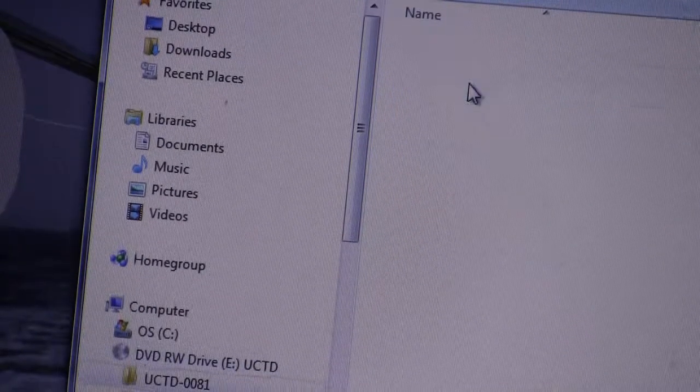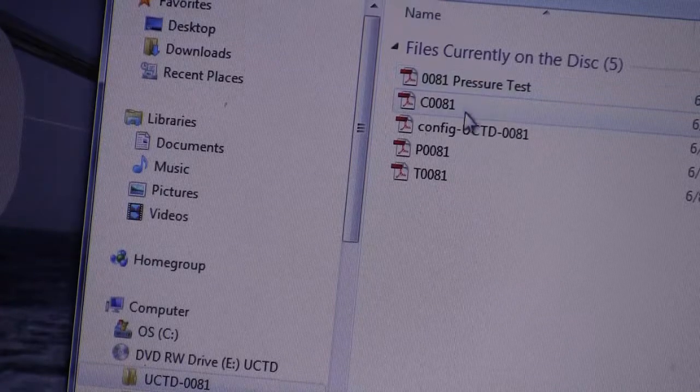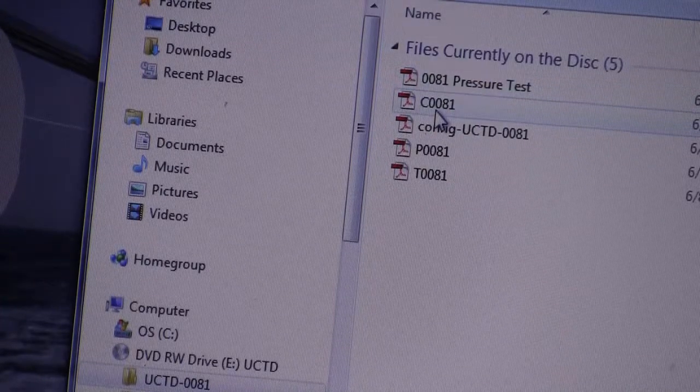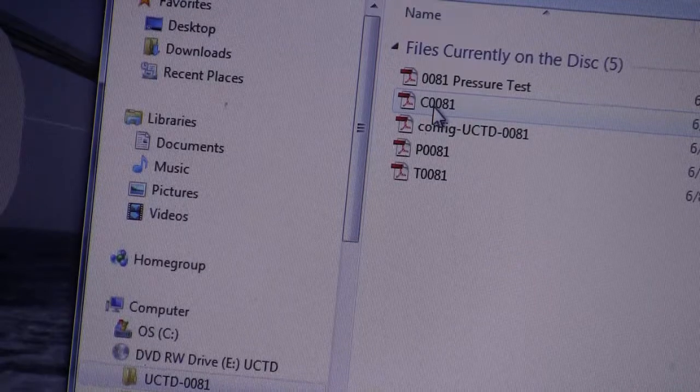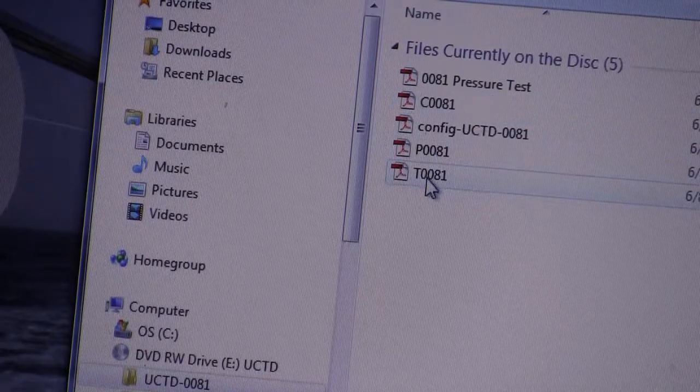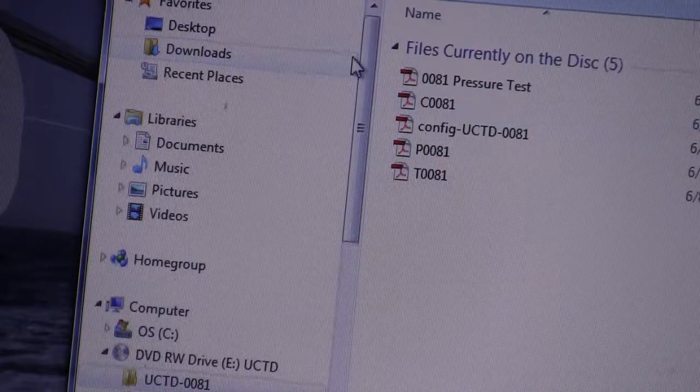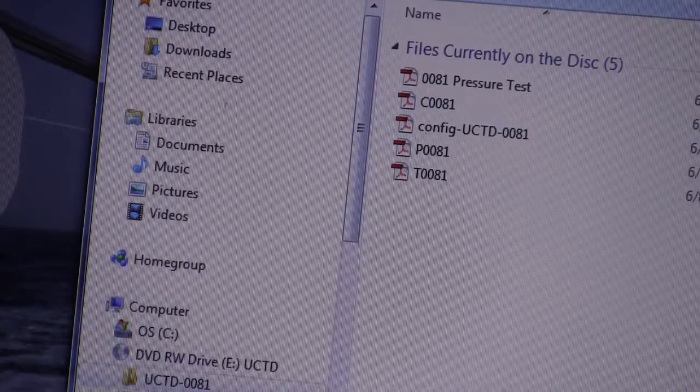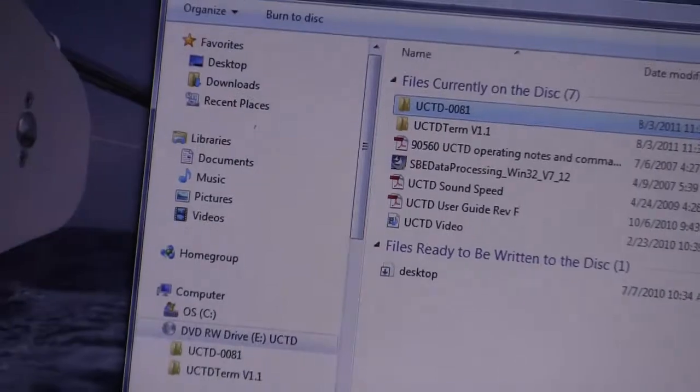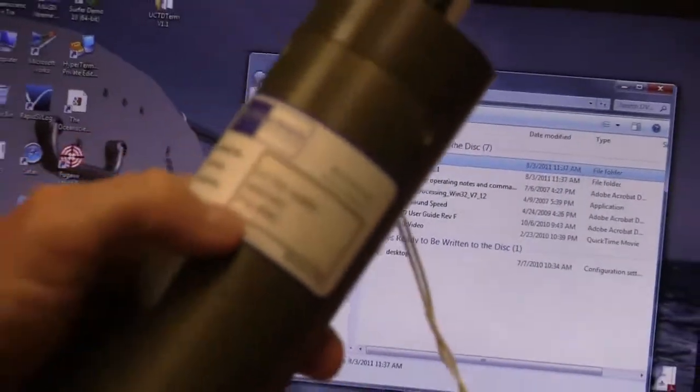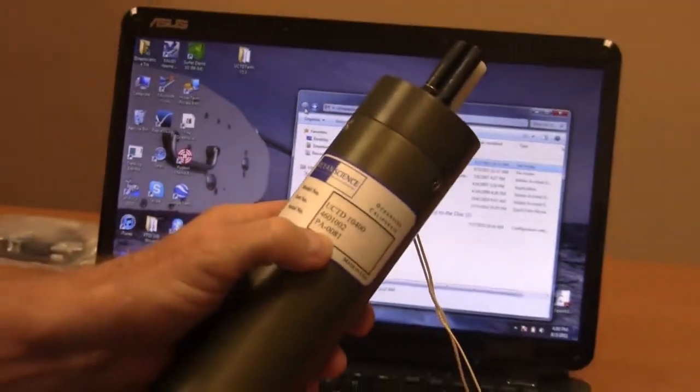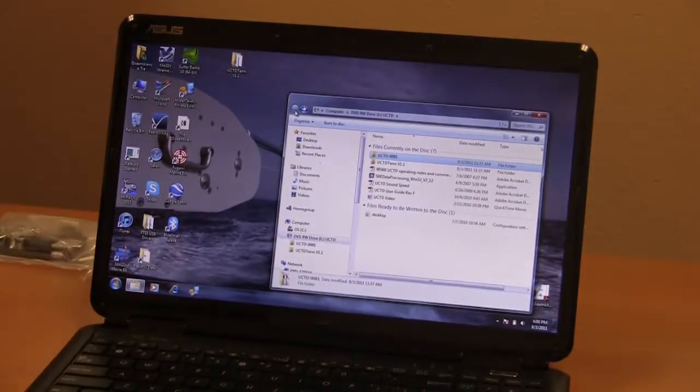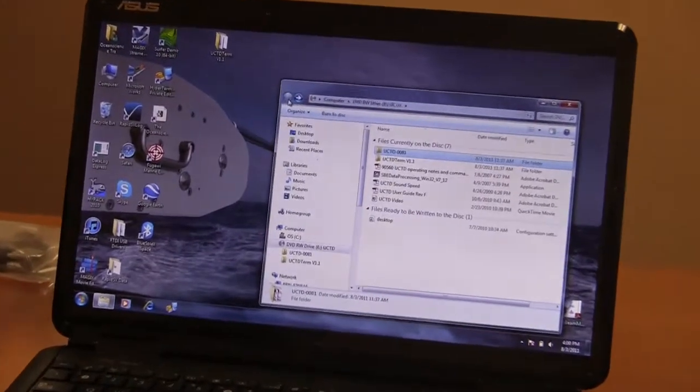If we open that, you can see there's the pressure test, the configuration, and the calibration documentation for conductivity, pressure, and temperature. That probe serial number is 81 and it will be marked on the probe somewhere. You can see right here. That's probe assembly 0081. That matches the calibration information.